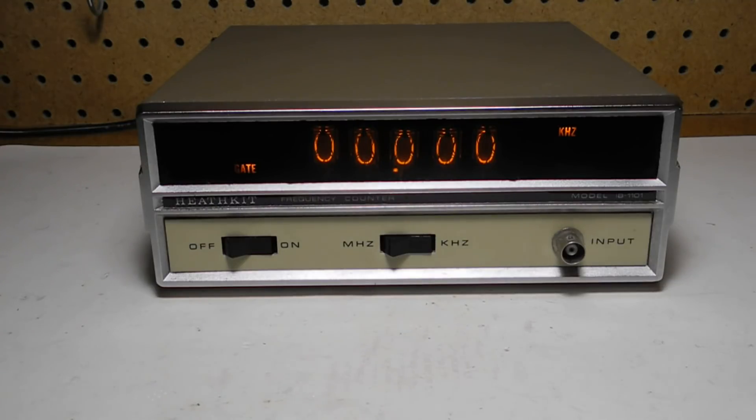The input impedance is 1 megohm shunted by less than 15 pF. The maximum input voltage is 250 V RMS from 0 to 5 MHz, decreasing to 3 V RMS at 100 MHz, and it can take a maximum of 250 V DC. It has an internal time base that after about a 30-minute warm-up has a stability of plus or minus 3 parts per million from 45 to 90 degrees Fahrenheit.